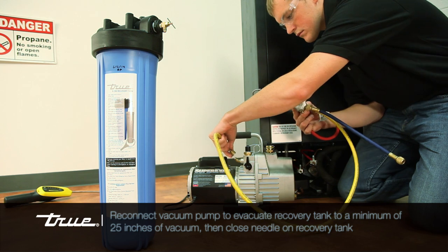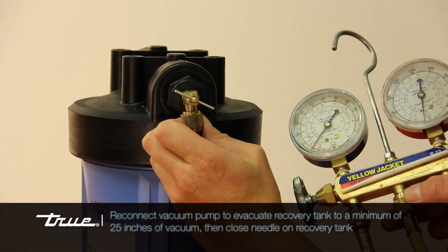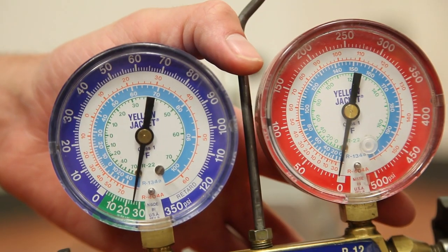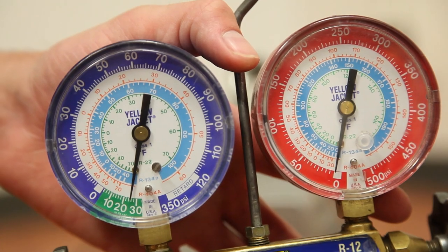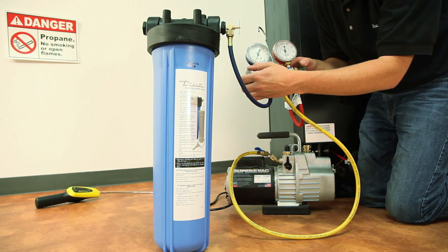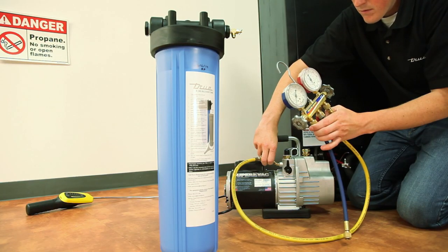Reconnect the vacuum pump and again evacuate the recovery tank to a minimum of 25 inches of vacuum. After a minimum of 25 inches of vacuum is achieved, close the needle valve on the tank along with the knob on your gauges, and disconnect the hoses from both the tank and the vacuum pump.